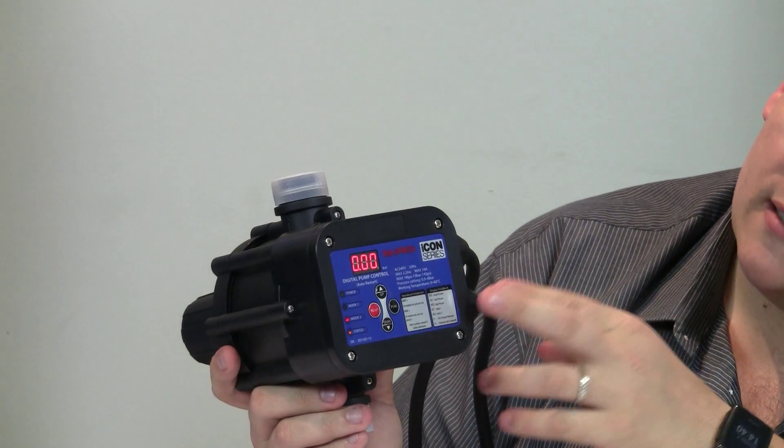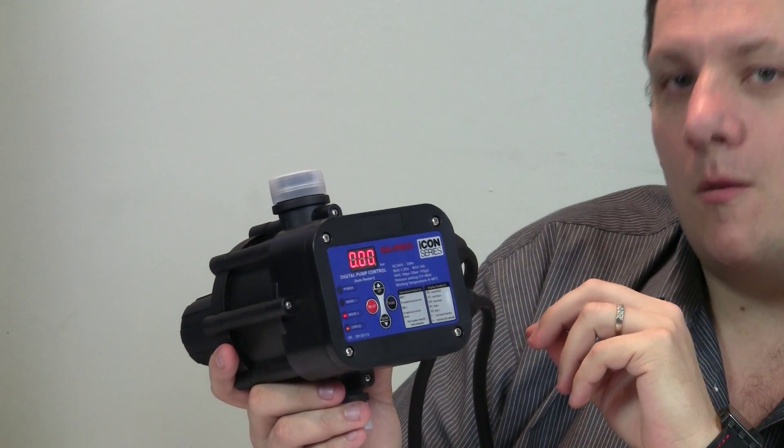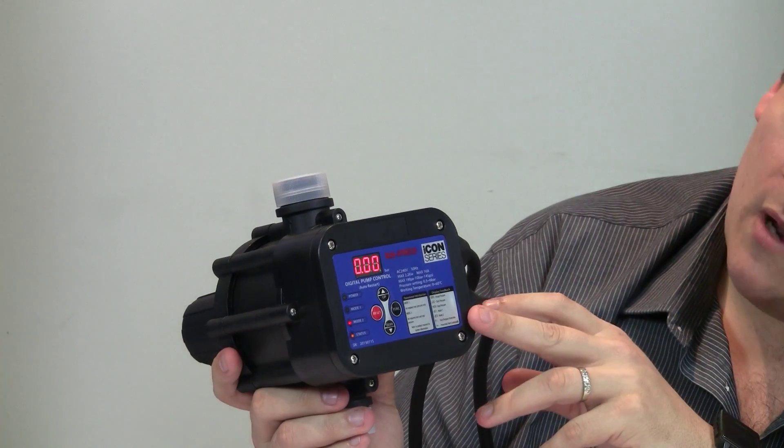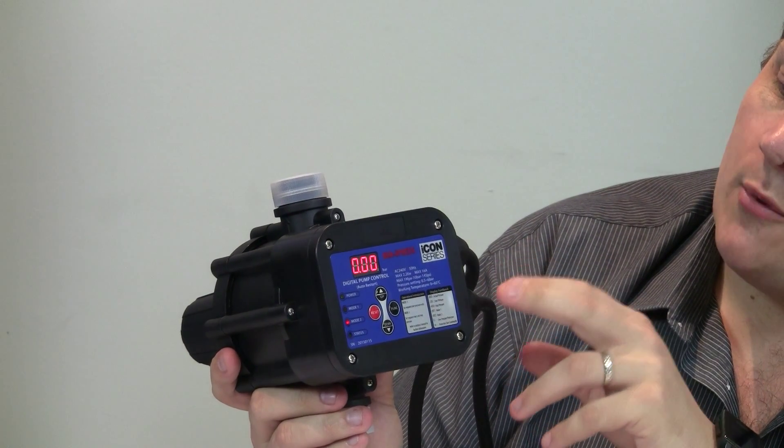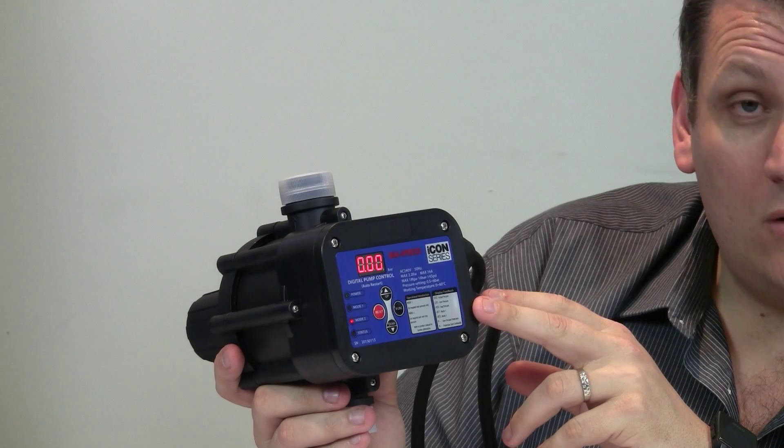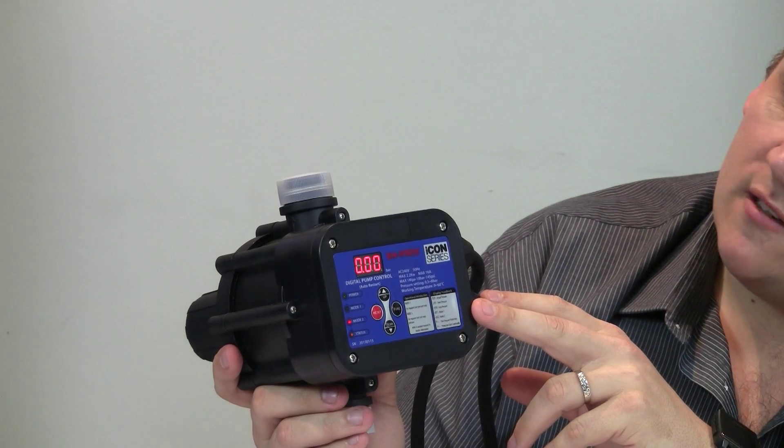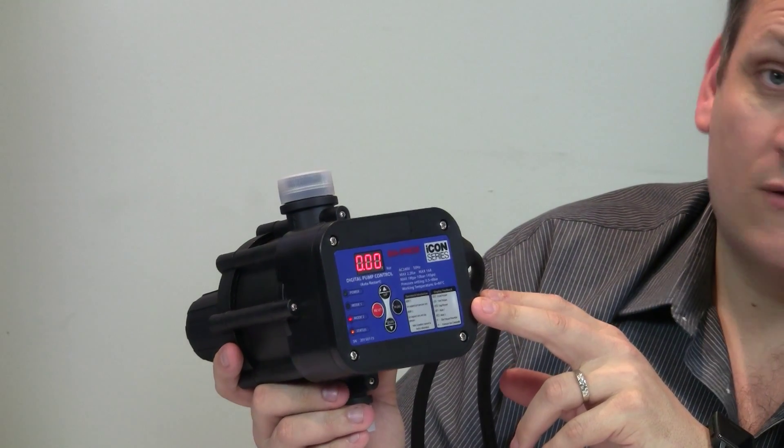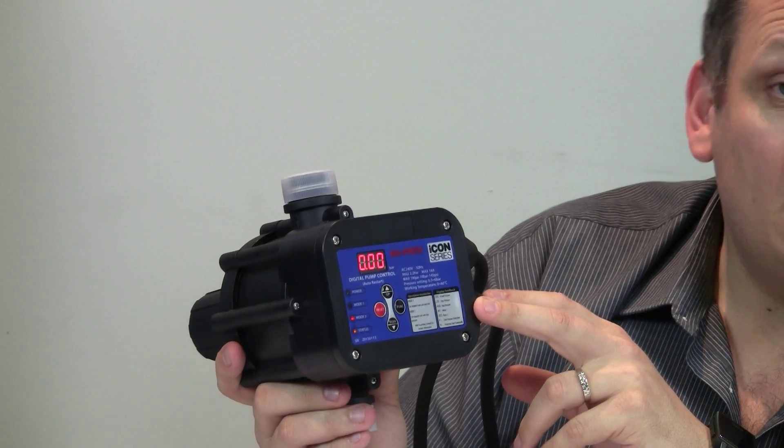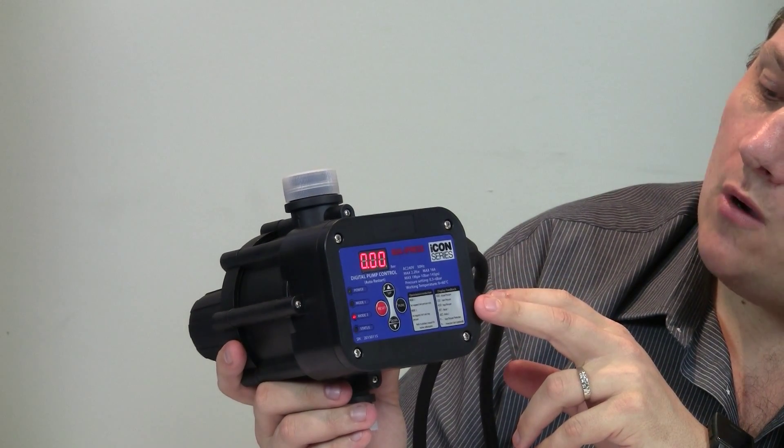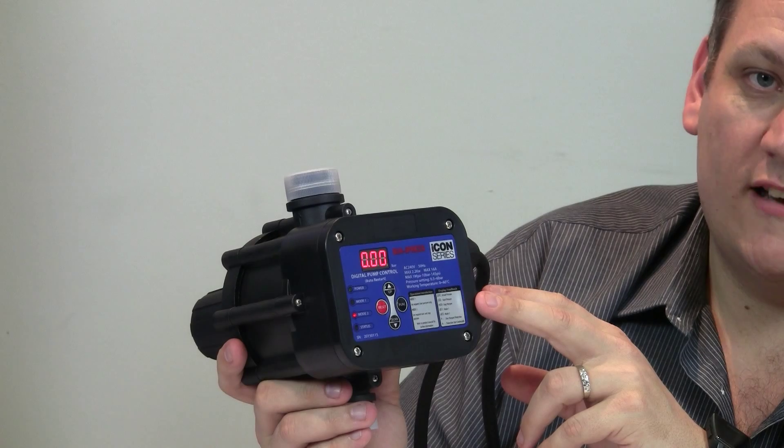The first of which is that it has two distinct operating modes. Mode 1 is operated as a standard pressure control with an adjustable cut-in pressure down to 0.6 bar, meaning that this particular control can control a wide variety of pumps.